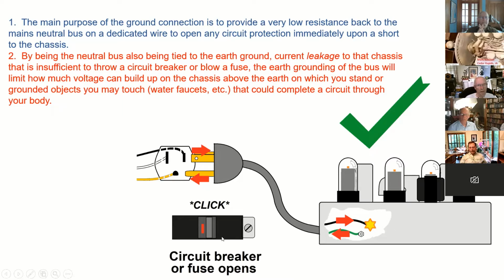100 milliamps leaking, it's not going to trip that circuit breaker unless there's a dead short. But if the radio chassis is grounded, it would help pull that down so that the current would flow to ground instead, even though there's some resistance there, because maybe it's just a transformer leaking to its cabinet and then back to the chassis.